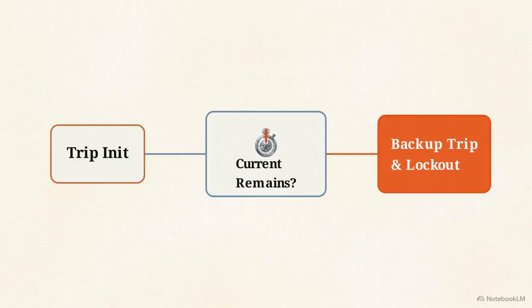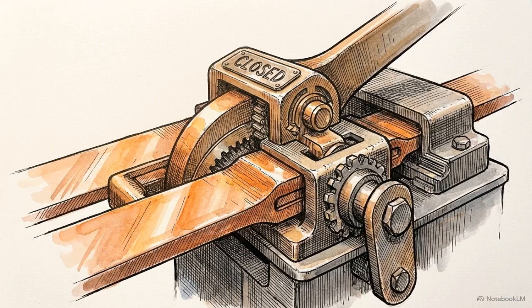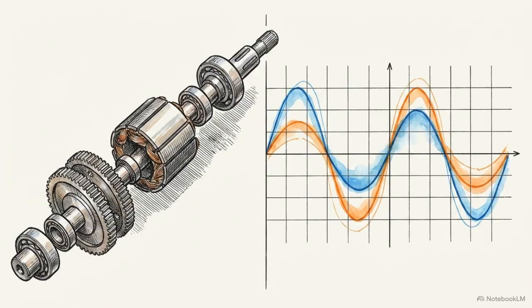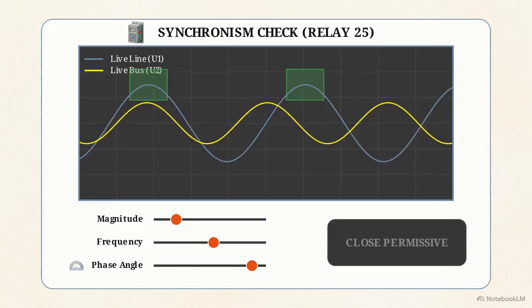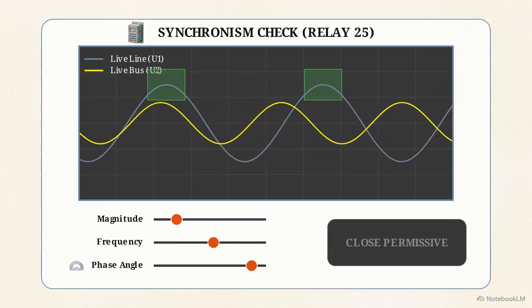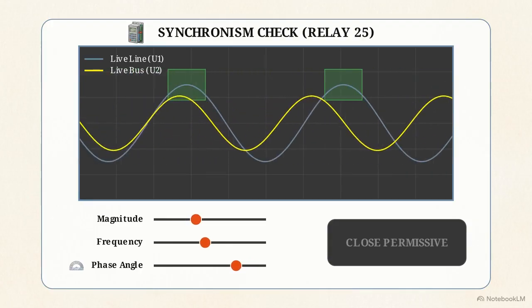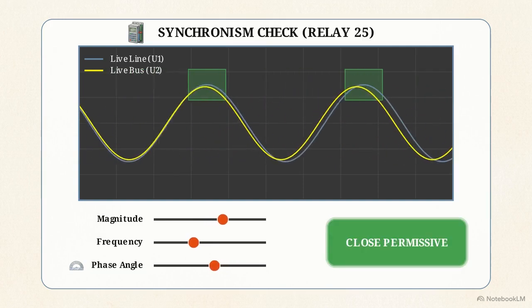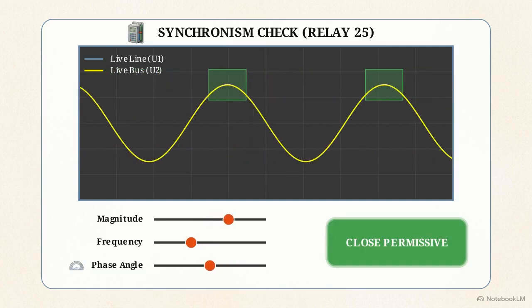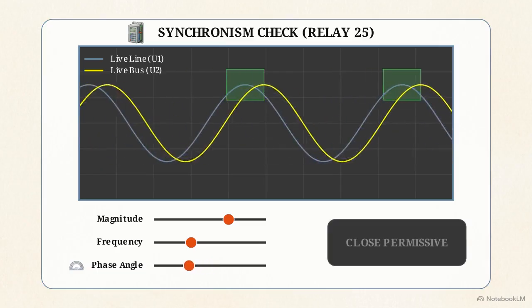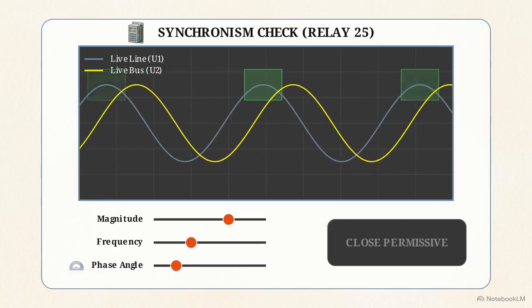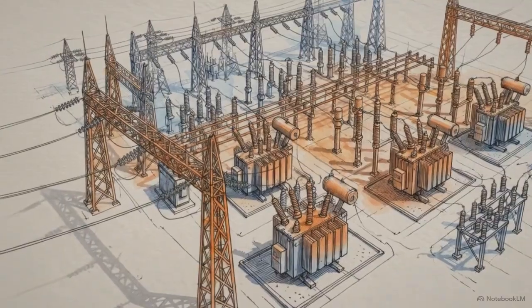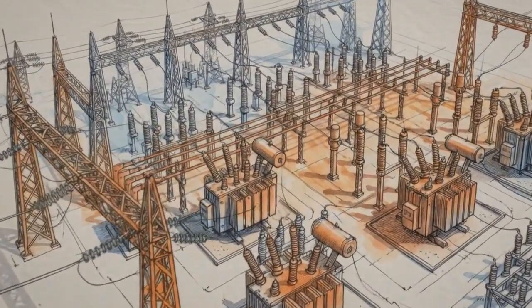Once a fault is cleared, the system must reconnect. Synchronism check, or 25 relay testing, prevents mechanical shock to the generators by mathematically aligning grid sections before permitting a re-energizing close command. To test this, technicians inject live line and live bus voltages into the relay. They alter the magnitude, frequency, and phase angle to pinpoint the narrow window of alignment that permits a close and the specific boundaries that block it.